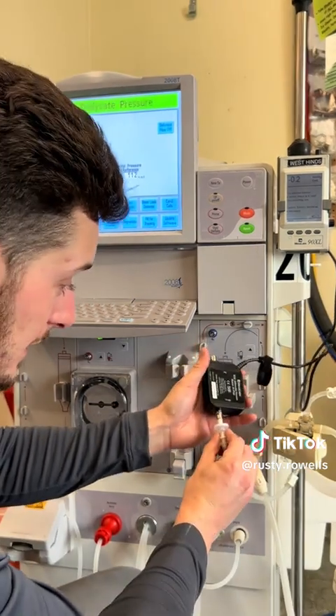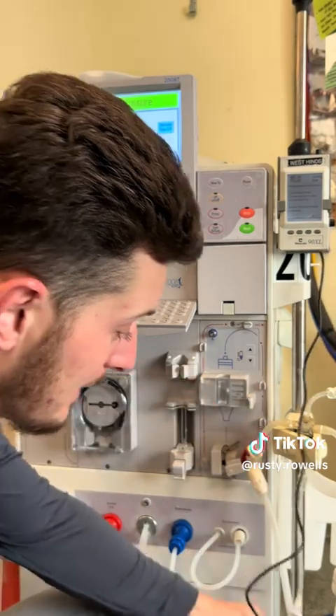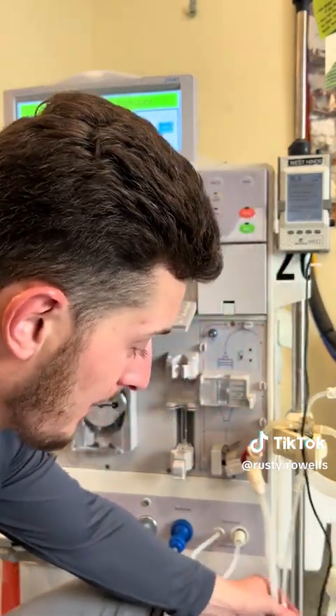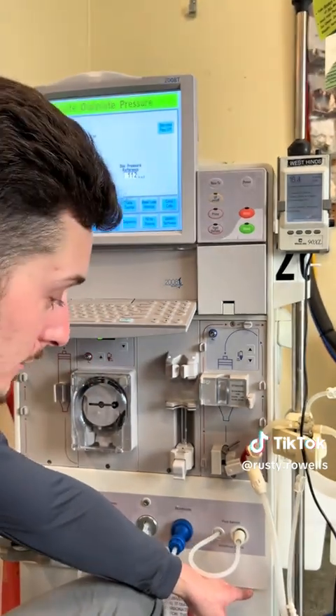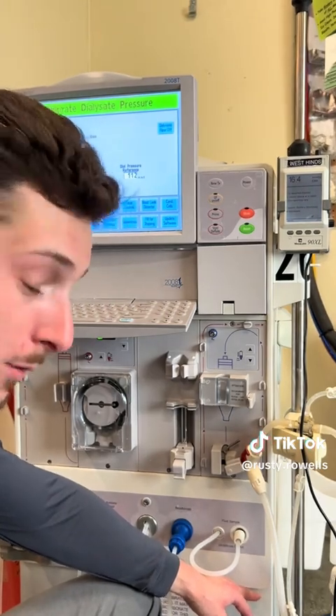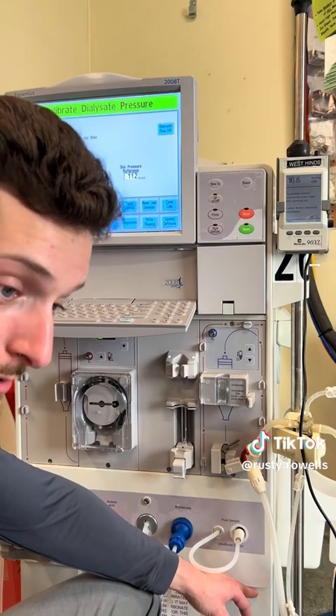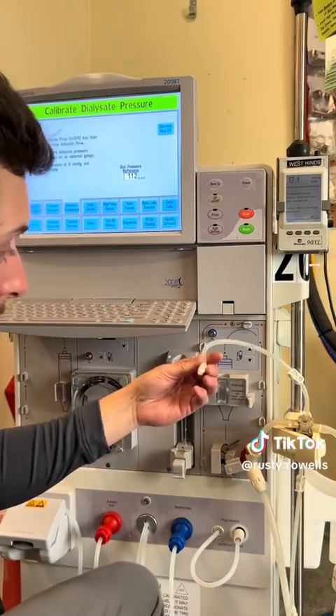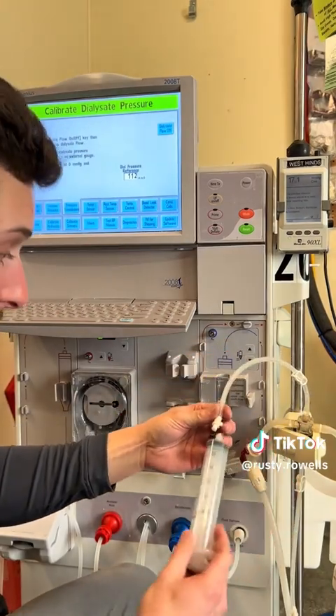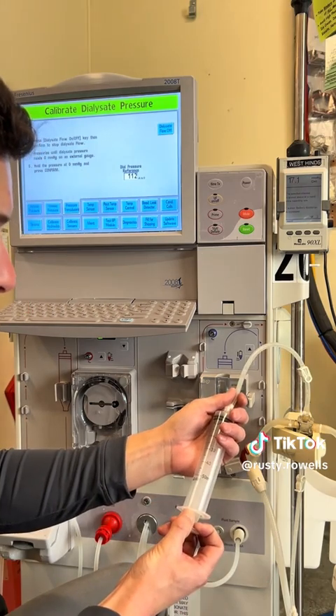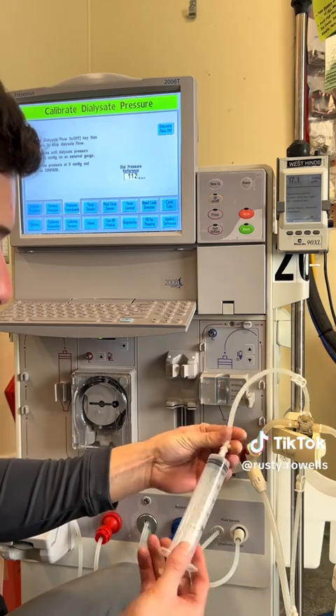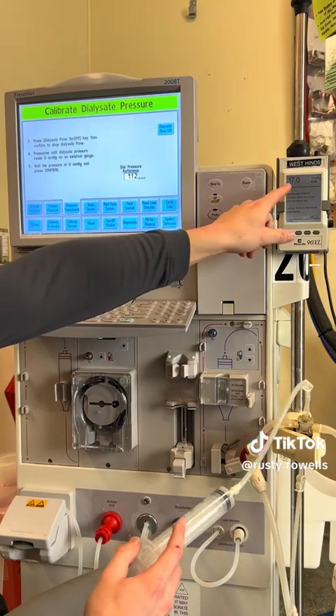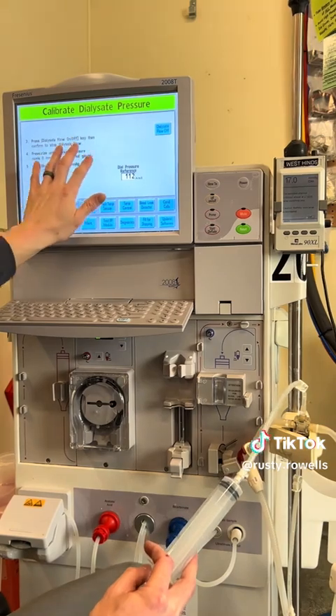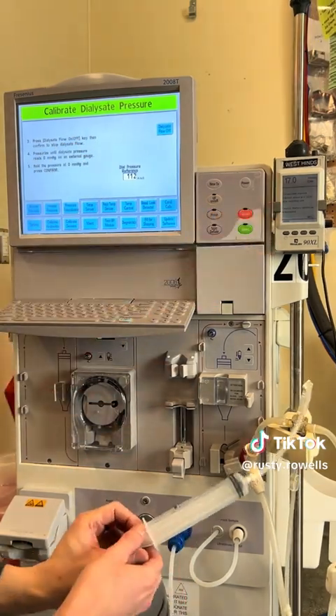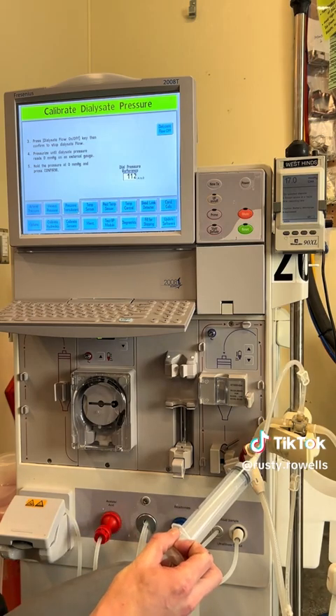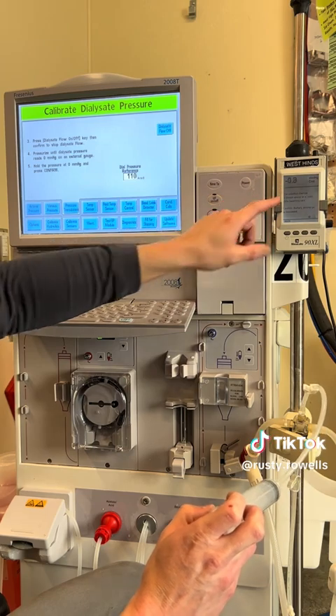So what we're going to do is just connect it up. What I like to do is leave it hanging because that is about the height of the transducer that we're getting ready to calibrate. The transducer that we're calibrating is the dialysate pressure transducer, which is number 9. Now, the other side is going to go to a 50 milliliter syringe. What I like to do is pull a little bit back and then connect it up. Reason being, we've got to zero this out right here. So we need to tell the machine what 0 is on the meter. So we're going to pull back where it's 17. And then all we do when this meter hits 0 is hit enter.